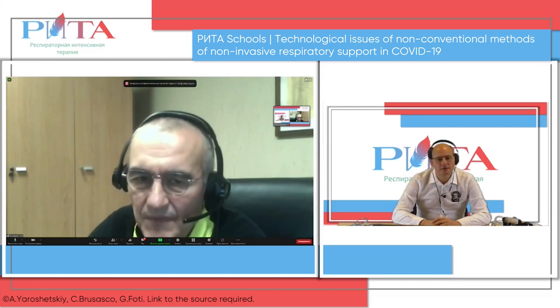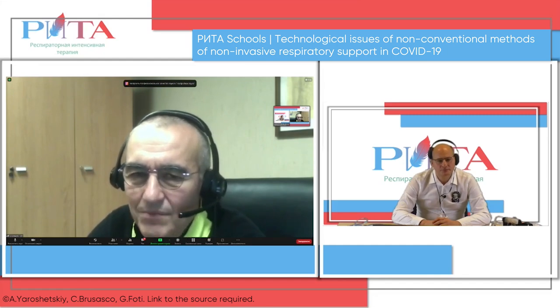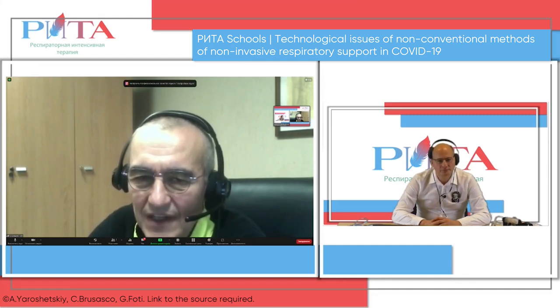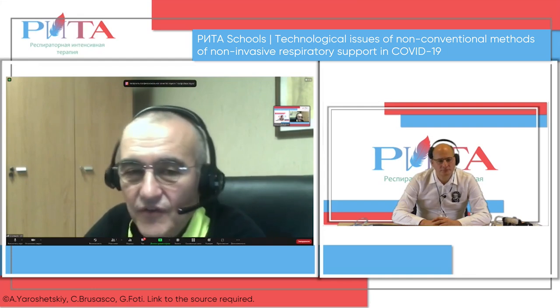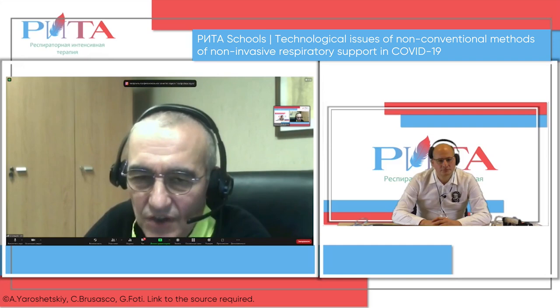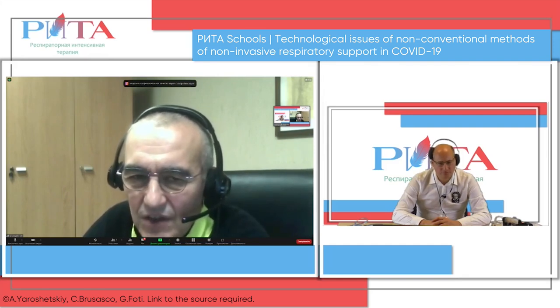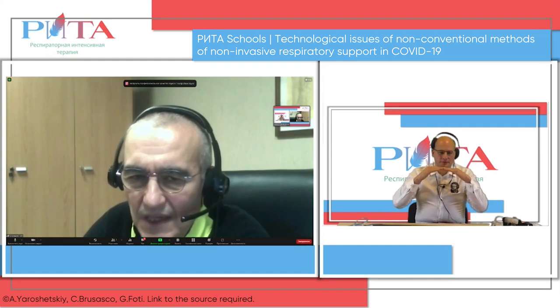Do we have differences between a turbine-based ventilator and a gas compression ventilator? In the past, yes. Now, high level turbine ventilators, not home ventilation ones, but standard turbine ventilators provide very good flow, comparable with the Venturi system. They are also stable, you just have to check the pressure inside the circuit.